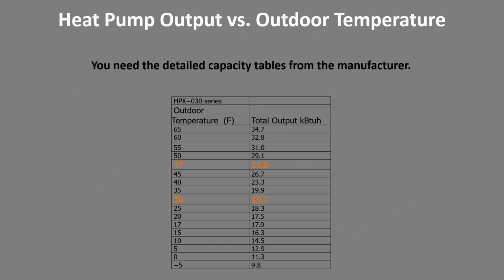This is a very detailed capacity output chart for a particular manufacturer. Some of you probably recognize. This is going to be their 2.5-ton system, and the 2 AHRI rating points, 47 and 30. We can see that it gives you 28K at 47 and about 19K at 30. To size right, you really do need the detailed capacity tables from the manufacturer.